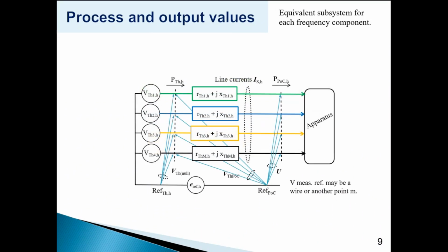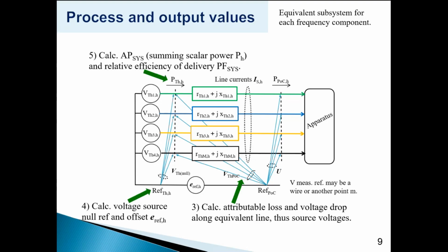So let's replace that with a conventional system diagram. We take the measurements of voltages at the reference point, at the POC, point of connection, and we measure U, and we express that as the RMS value of magnitude and angle. From that, we can look back through the equivalent impedance to the voltages at the equivalent source as measured from the point of connection. Then we look at step 4, calculating the voltage source from a reference point at the voltage source. And that reference point is defined by Kirchhoff's voltage law.